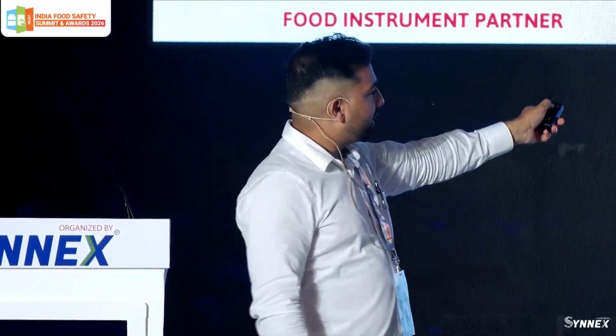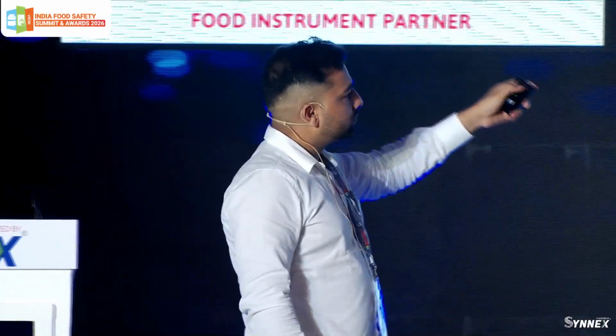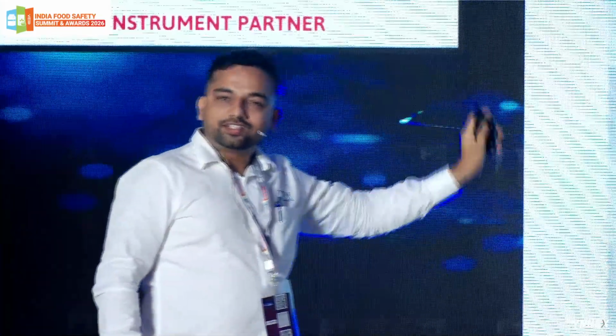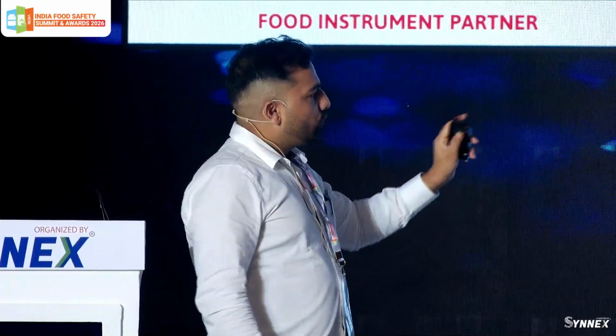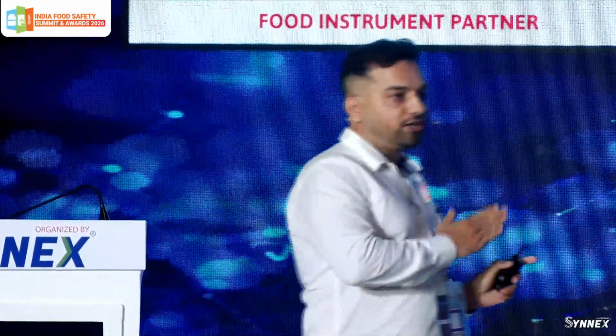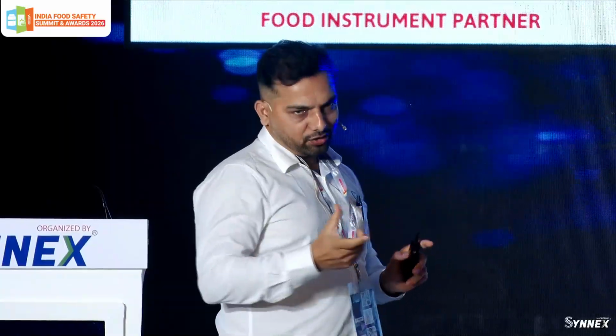Protein, with Kjeldahl, takes 3.2 hours. If you use the Sprint, 3 minutes. Again, it is checking only amino acid nitrogen, not nitrogen from urea or melamine. Moisture: some of you might be using a halogen moisture analyzer, but if you are going from 0.5 to 100% moisture, you will have limitations. Here we use the microwave. CEM is specific for the microwave.